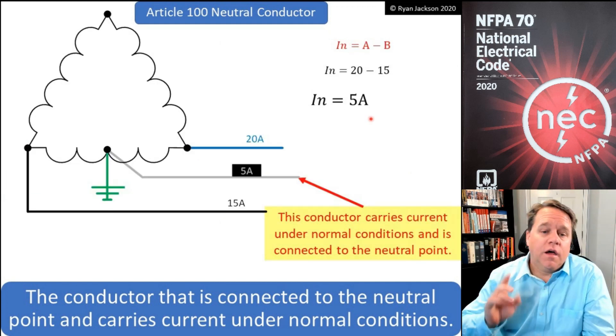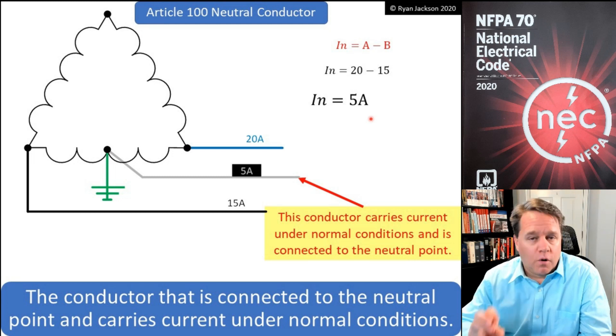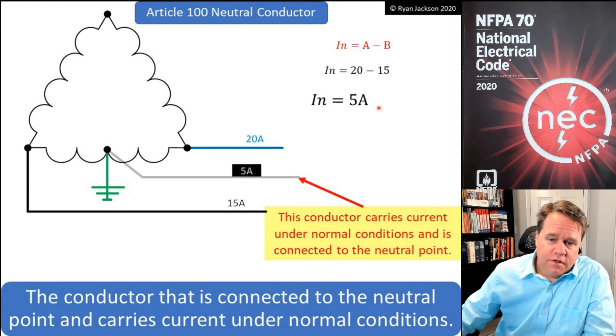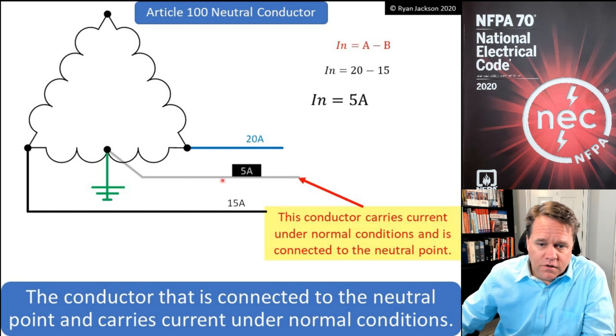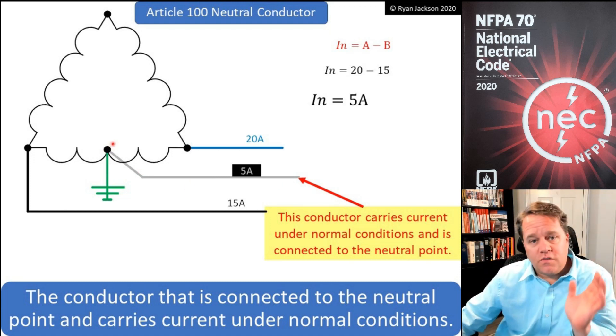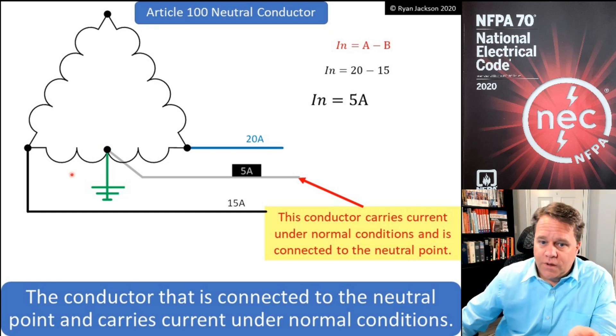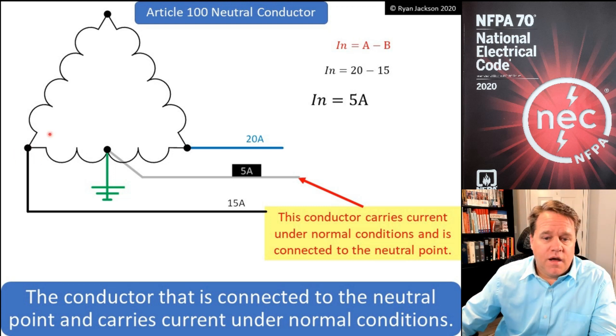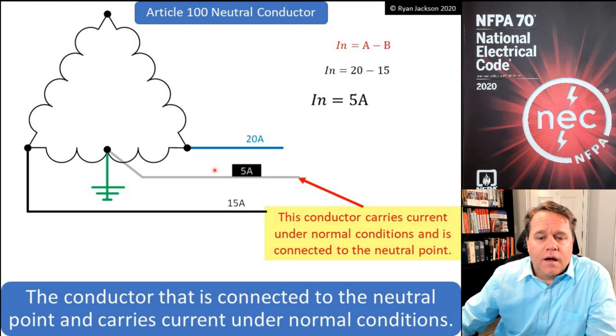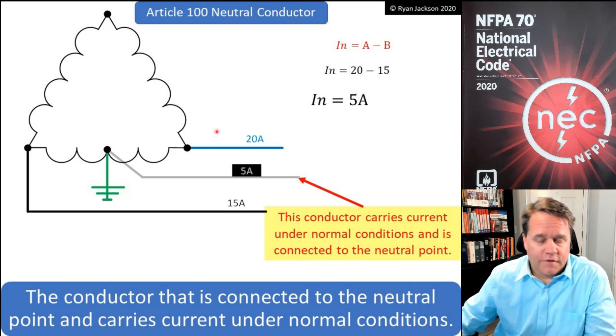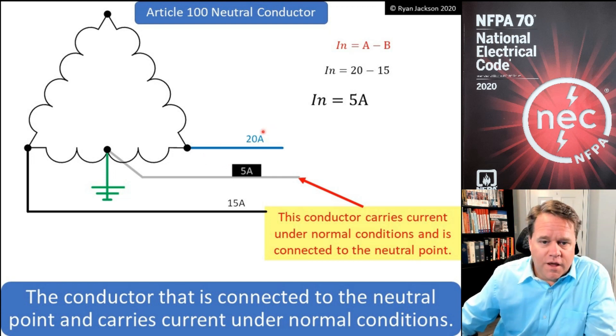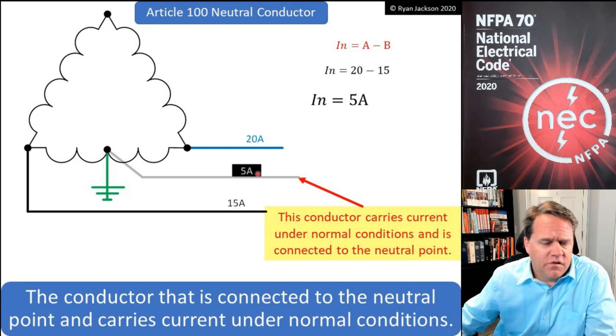On a three-phase four-wire delta connected system, the neutral conductor is connected to the neutral point and carries current under normal conditions — that's a neutral conductor. To determine the neutral current on this system, you simply take Phase A minus Phase B, and that difference is your neutral current. So with 20 amps on one phase and 15 amps on the other, you have 5 amps on the neutral — nice and easy.